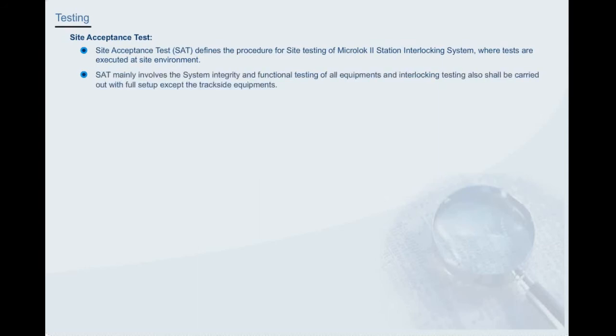Site acceptance test mainly involves the system integrity and functional testing of all equipments, and interlocking testing also shall be carried out with full setup except the trackside equipments. Site acceptance test is carried out for each station separately. Results of the tests are observed and documented in a test report.